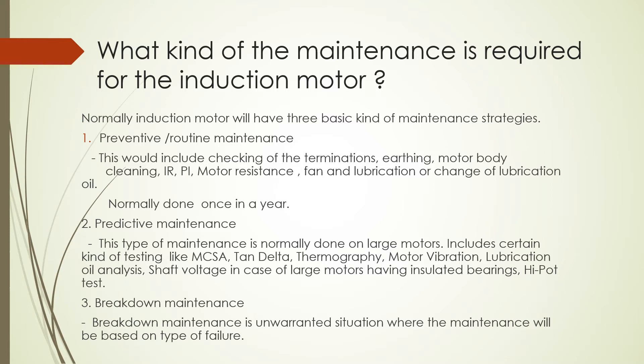Predictive maintenance is normally done on large motors and includes certain kinds of testing like MCSA, tan delta, thermography, motor vibration, lubrication oil analysis, shaft voltage — in case of large motors having insulated bearings — and hipot test. Breakdown maintenance is an unwarranted situation where the maintenance will be based on the type of failure.